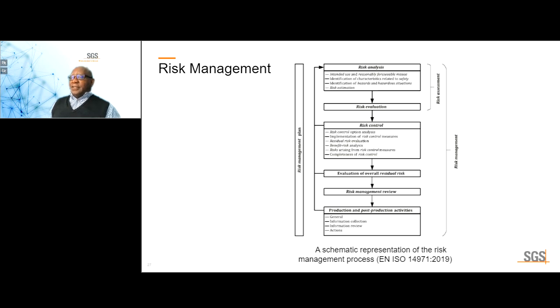Risk management. The truth of the matter is this. The MDR has risk analysis, risk management mentioned at least 250 times, which essentially means this regulation is a risk management regulation. And the harmonized standard for conducting risk management is EN ISO 14971-2019. And it typically covers a risk analysis, risk evaluation, risk control, and then you do your determination of residual risk and an overall evaluation of residual risks, because some of these things can then be listed either as warnings or contraindications in your IFU.